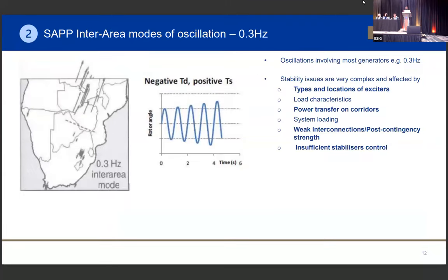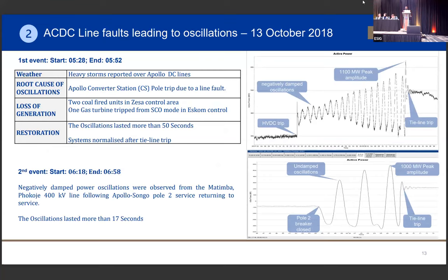Another type of mode that we have is a 0.3 mode. The group of ESKOM generators in the south tend to oscillate with the group of generators in the north because we have a weak link there. Stability issues that are very complex are affected by the location of exciters, power transfer, weak interconnections, and insufficient stabilizer control. One example that happened: we had a fault on one of the DC lines.